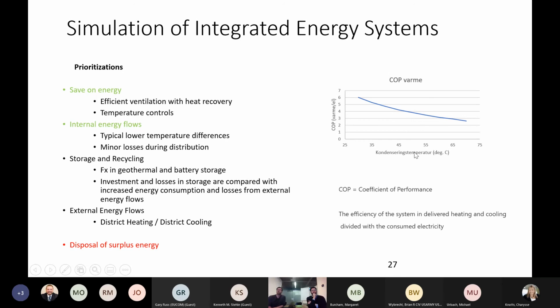One thing to keep in mind with heat pumps is the COP value that Drew was talking about, the coefficient of performance. This is the ratio of how much heat, or in principle how much cooling, you get out of using a certain amount of electricity. So this efficiency, or COP value, can be 6—that's an efficiency of 600%.